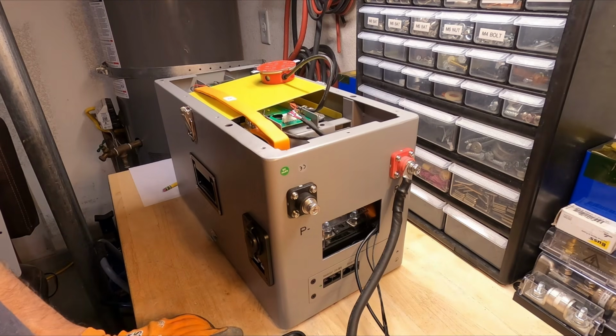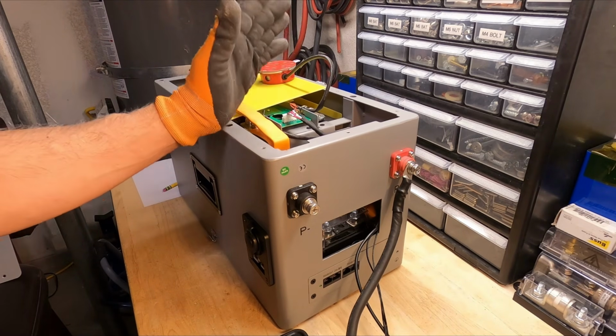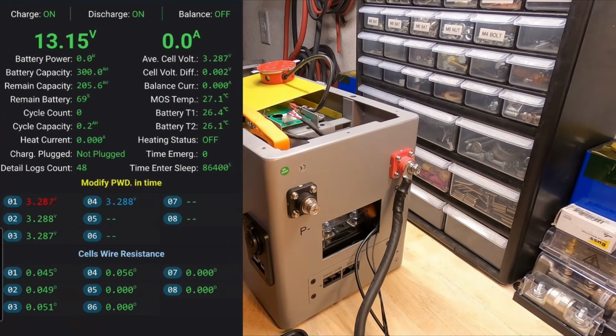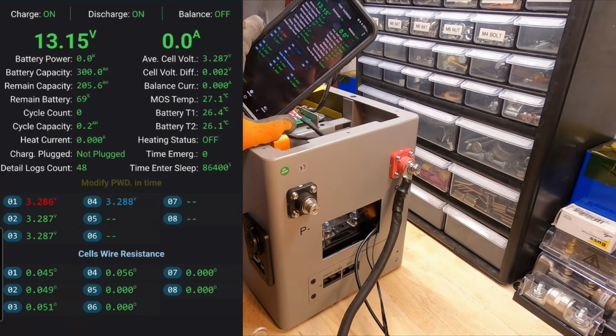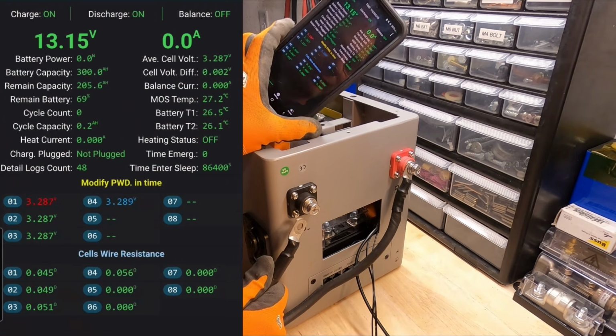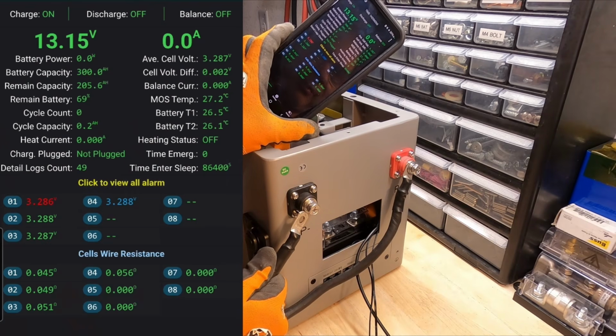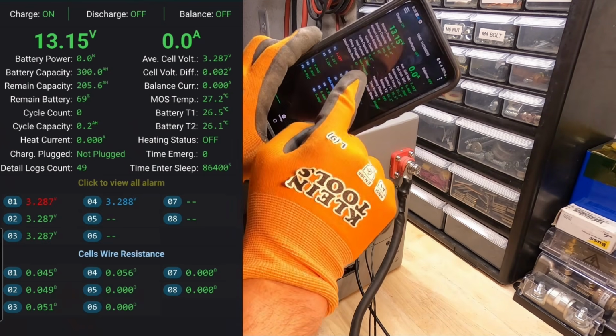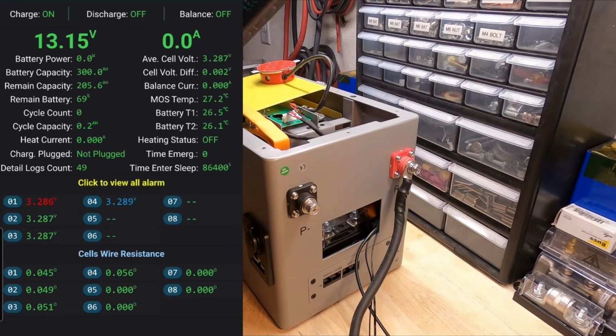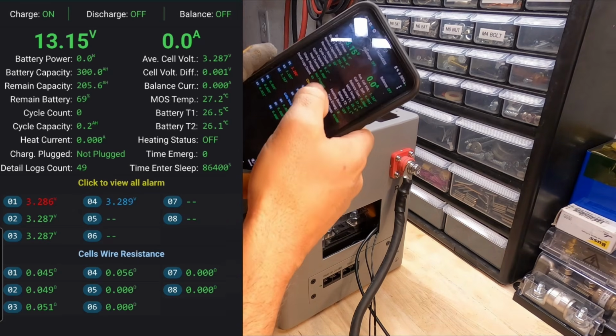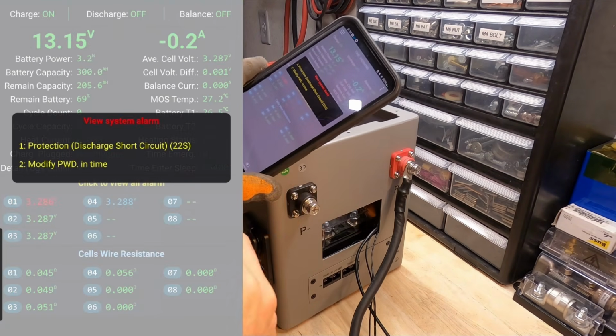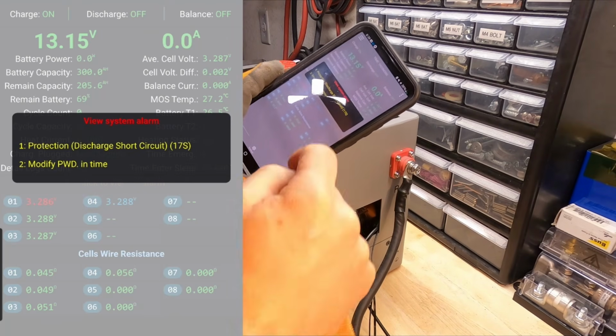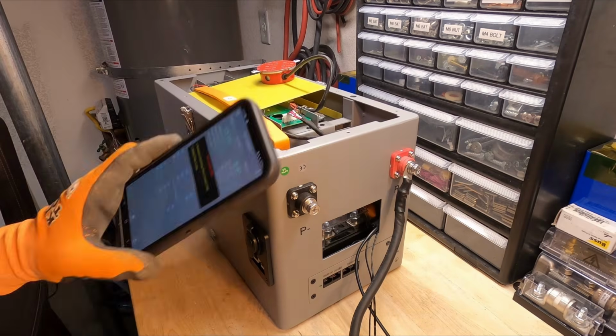Alright, so we got to prove that the short circuit actually does work on this thing. So we're just going to short circuit the terminals directly, and we're going to watch our BMS. There it is - there's our alarm. Protection, discharge, short circuit. And it will return in 20 seconds.